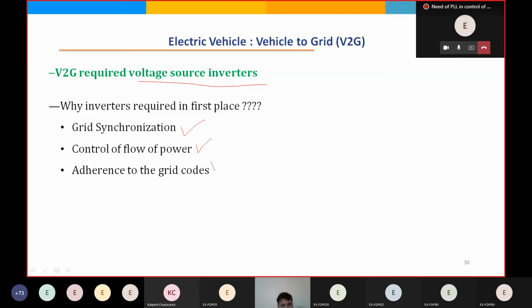When you connect the inverter to the grid, it has to follow certain grid codes. For distributed energy resources, there's an IEEE standard, 1547, that we have to adhere to. This specifies the THD level — when connecting a distributed energy resource through a voltage source inverter to the grid, the currents being injected must not have THD in excess of 5%, otherwise we'll have power quality issues.